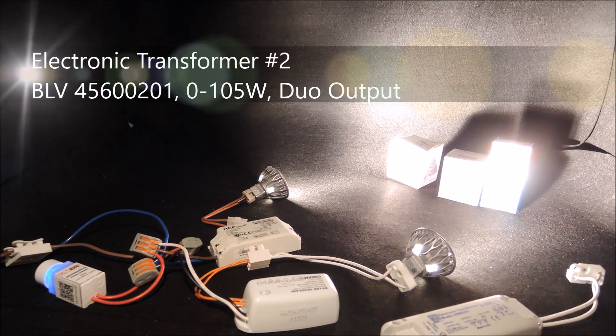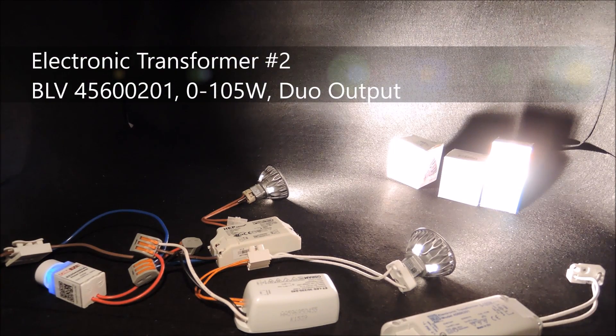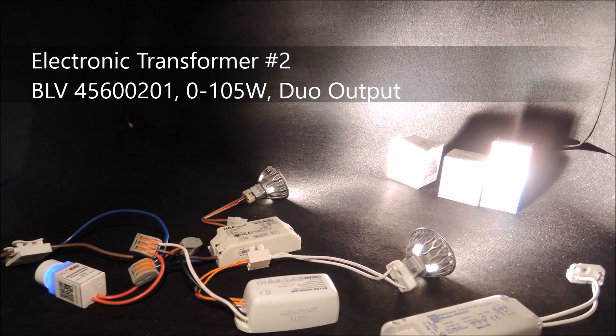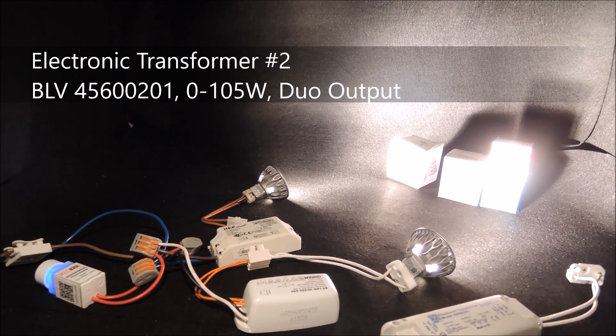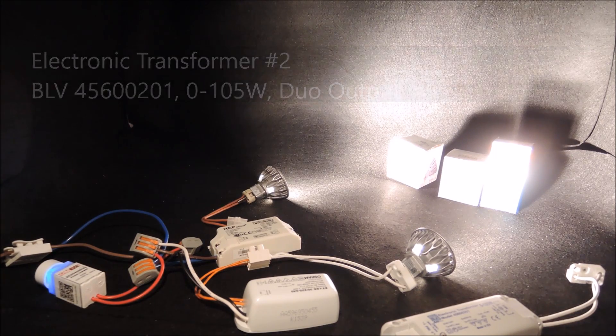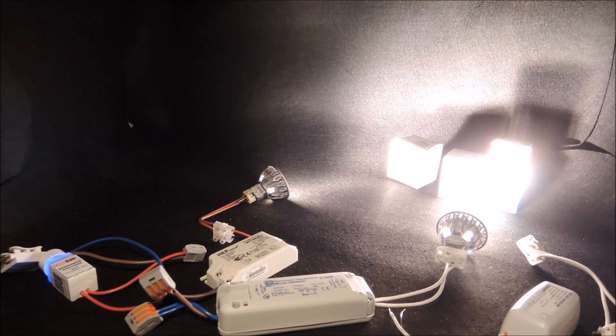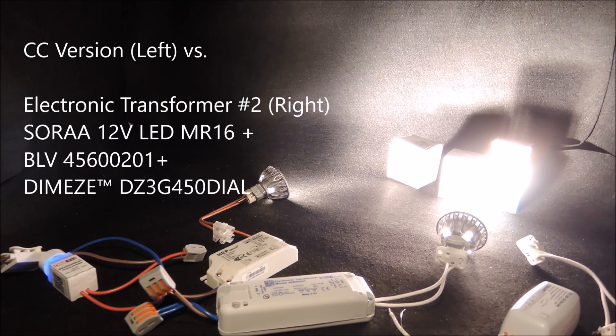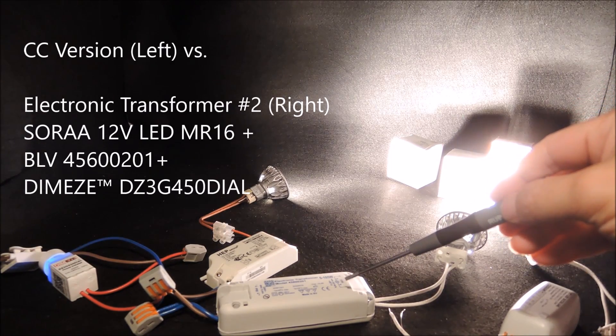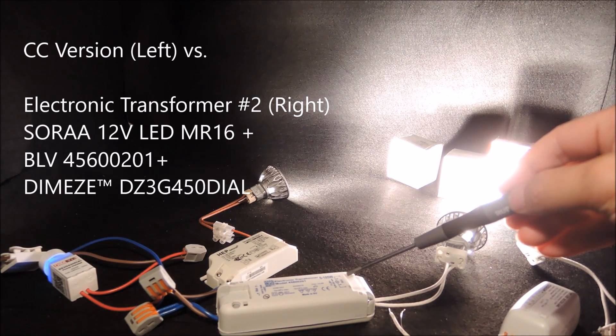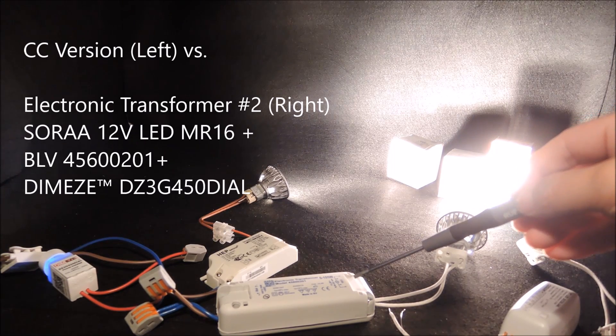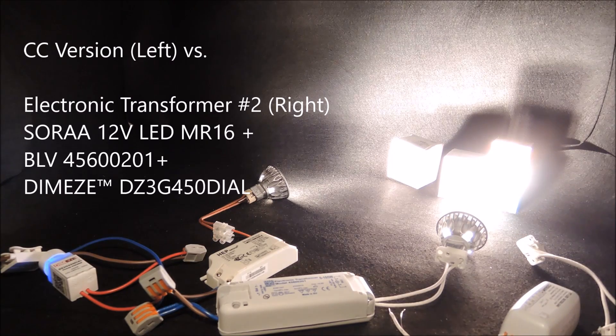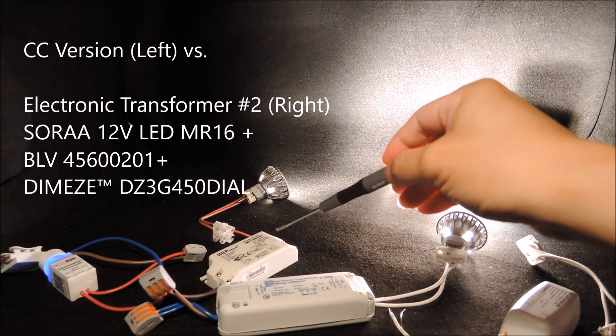In the following, we are going to change to the BLV 45600201, which is a 0-105W electronic transformer. We will see that the BLV 45600201 electronic transformer is capable of producing a deep dimming performance comparable to the constant current setup, which we have the HEP 10W driver as our baseline.